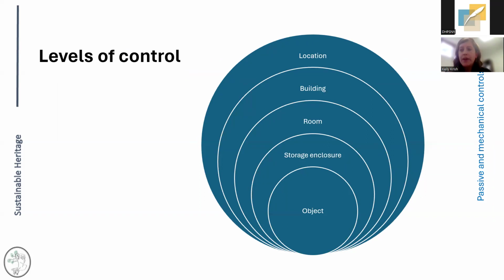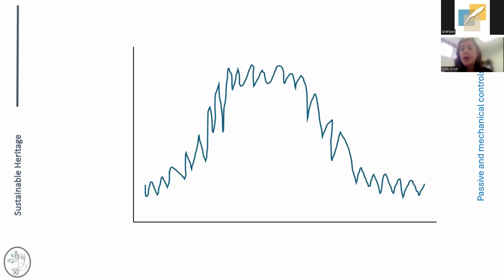And so that's how I would really recommend that we approach both data analysis more generally, but also from the perspective of dew point, is we kind of want to start with the outside and work our way in to see how we're controlling it at each of these points and how effective we are at managing our moisture levels. So you'll see this format a lot throughout here. I just did really straightforward graphs with no numbers on them. The general idea is just the visual trend to see what something could look like without having to worry about the specifics of it. But this is intended to be representative of what you might see if you pulled up a dew point graph of your outside air. So what's immediately outside your building.